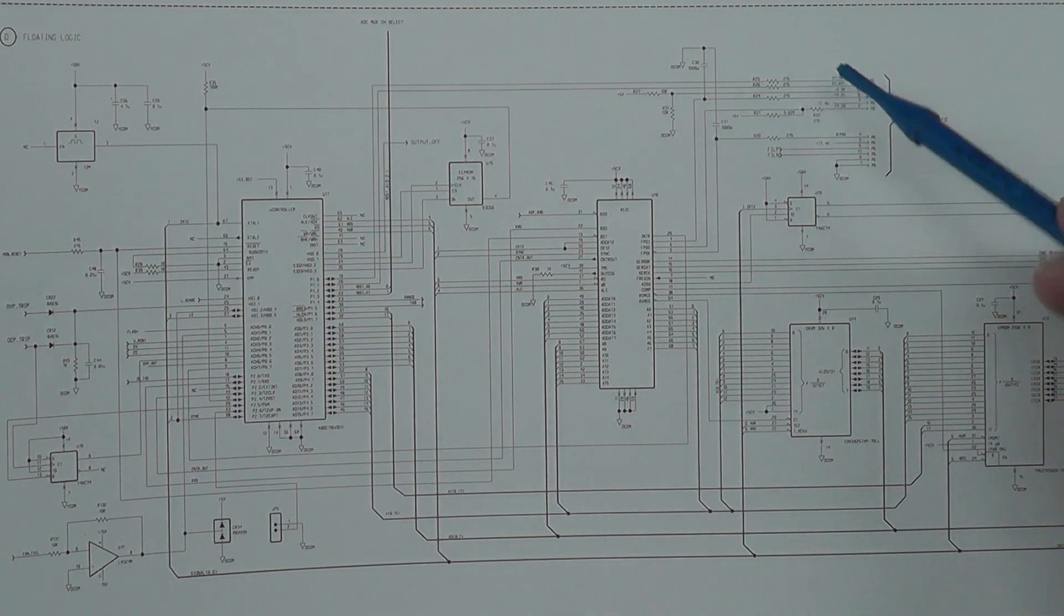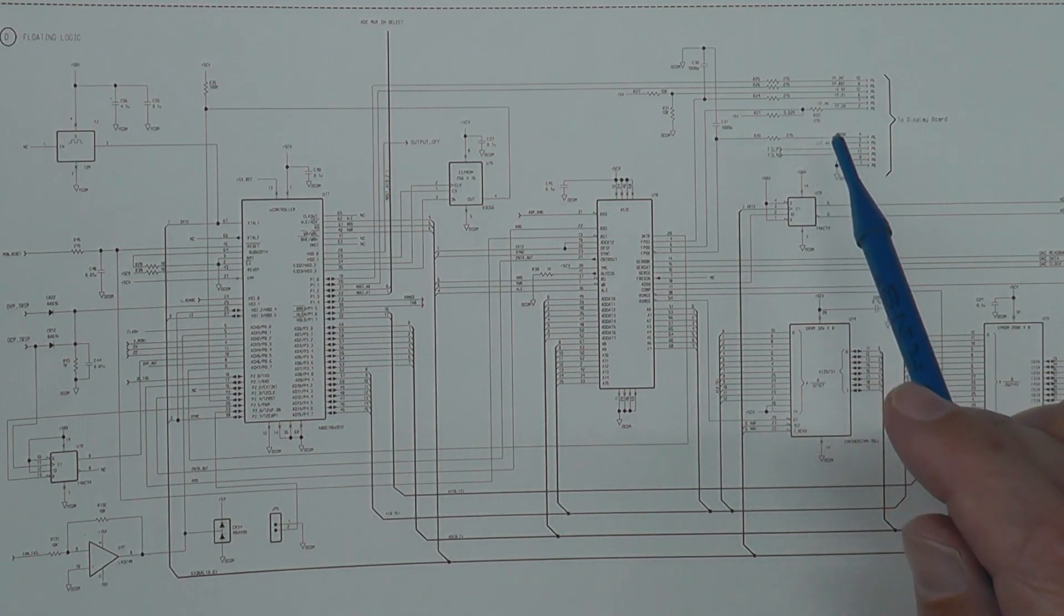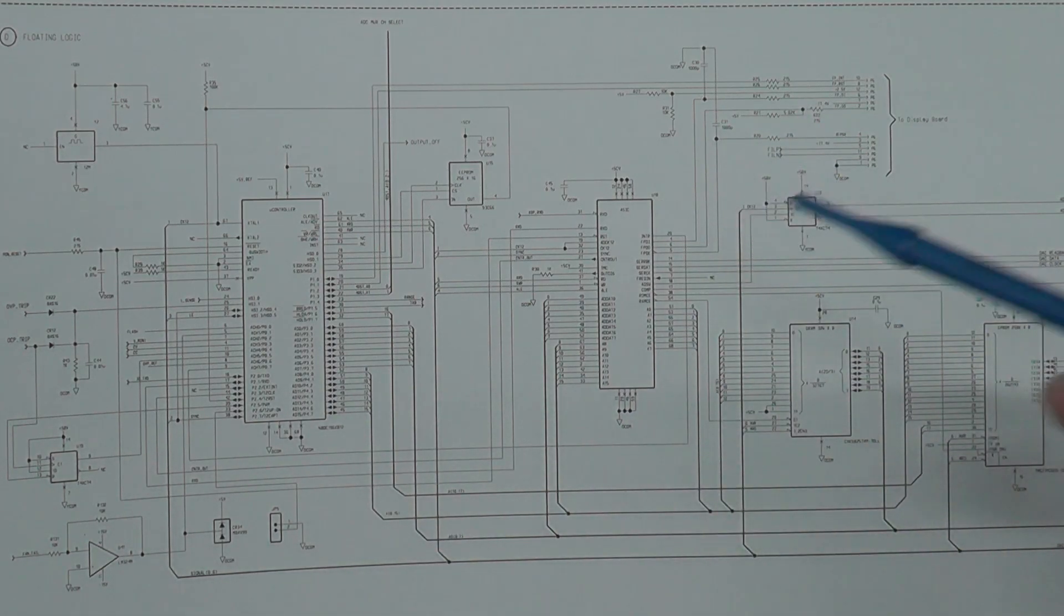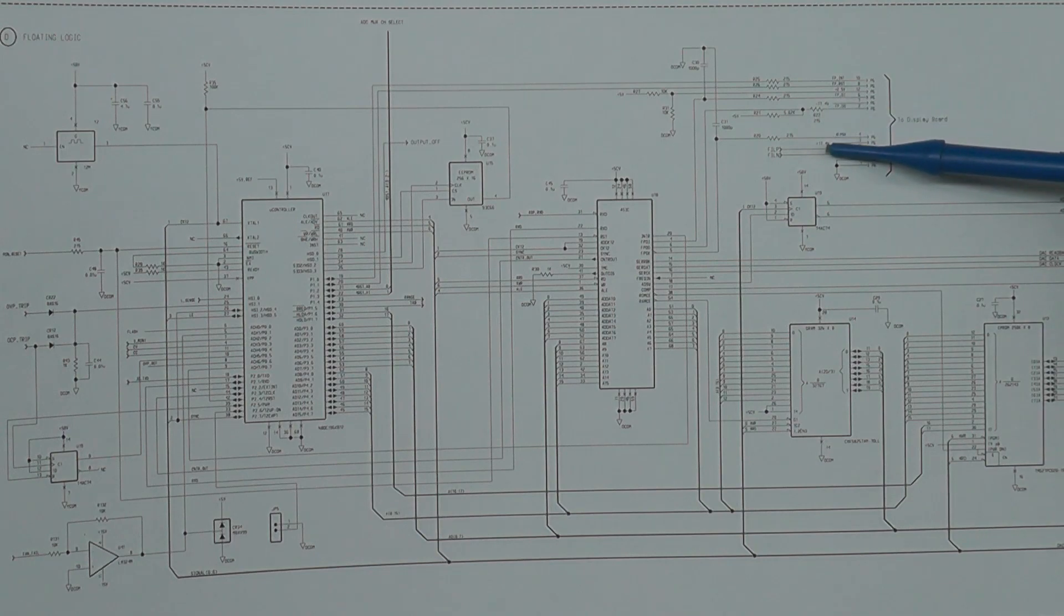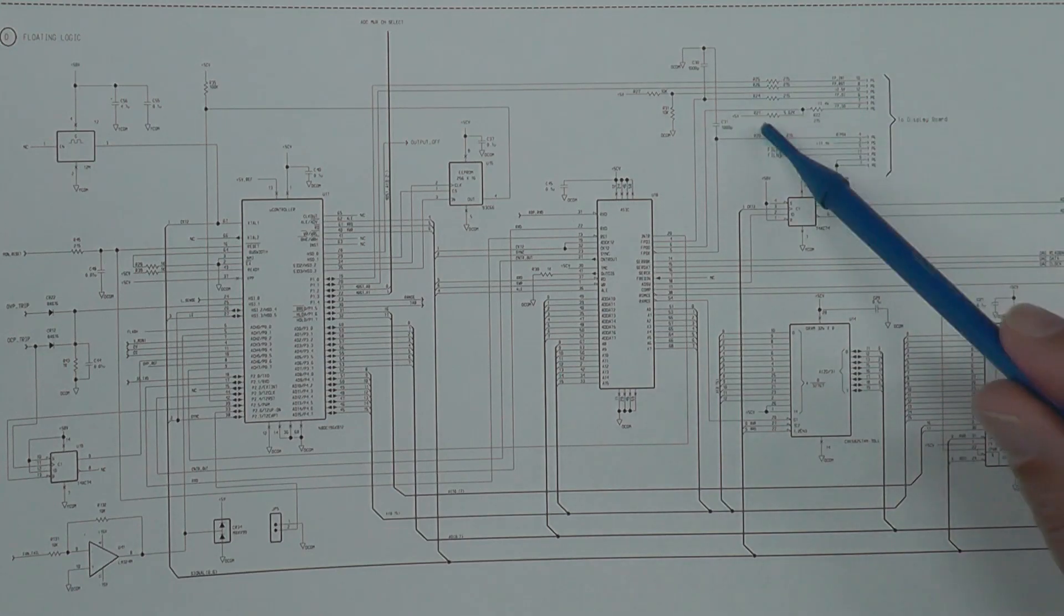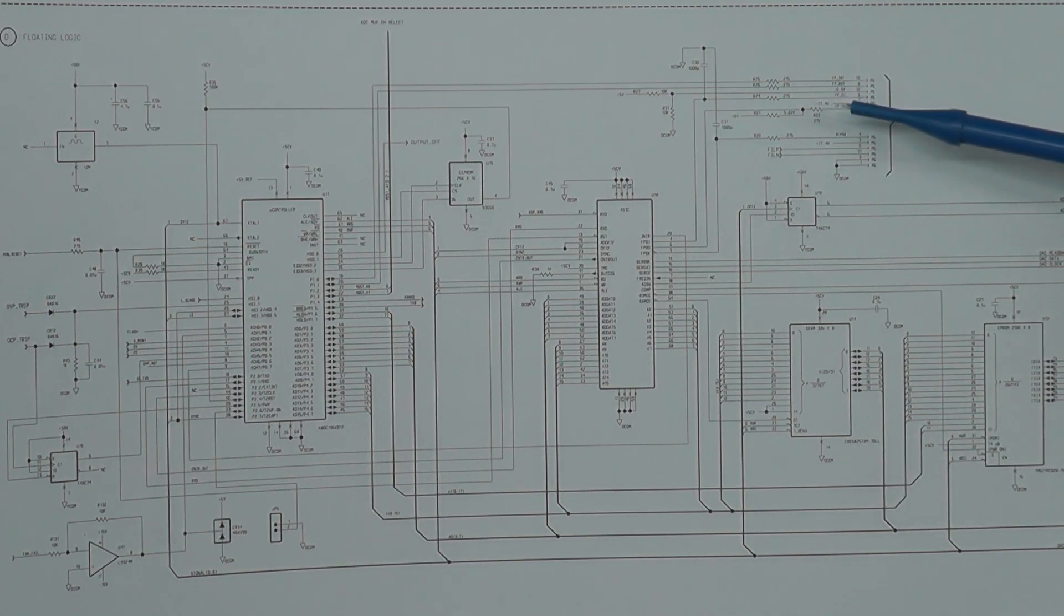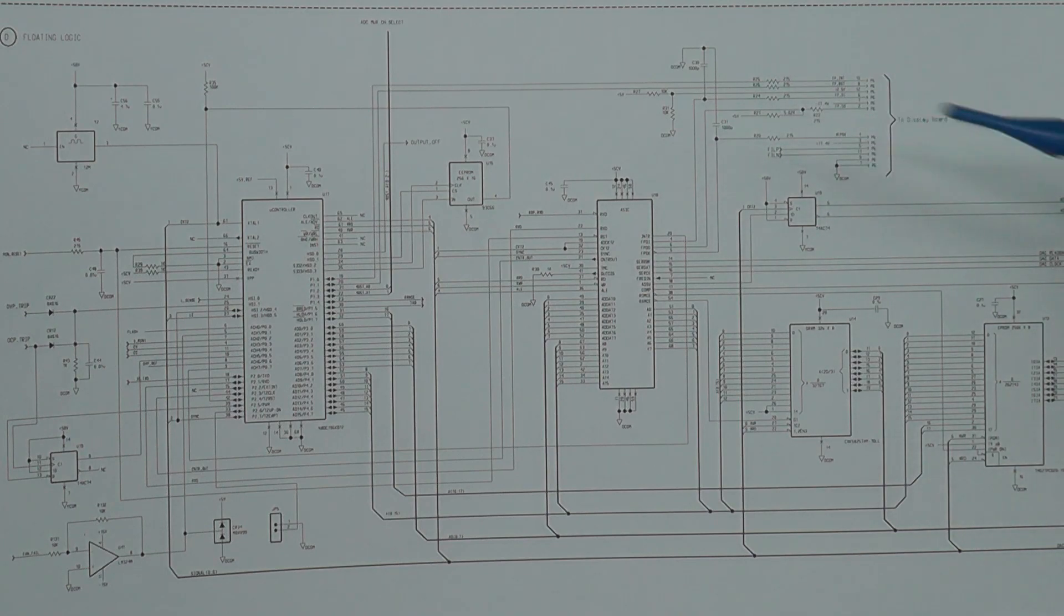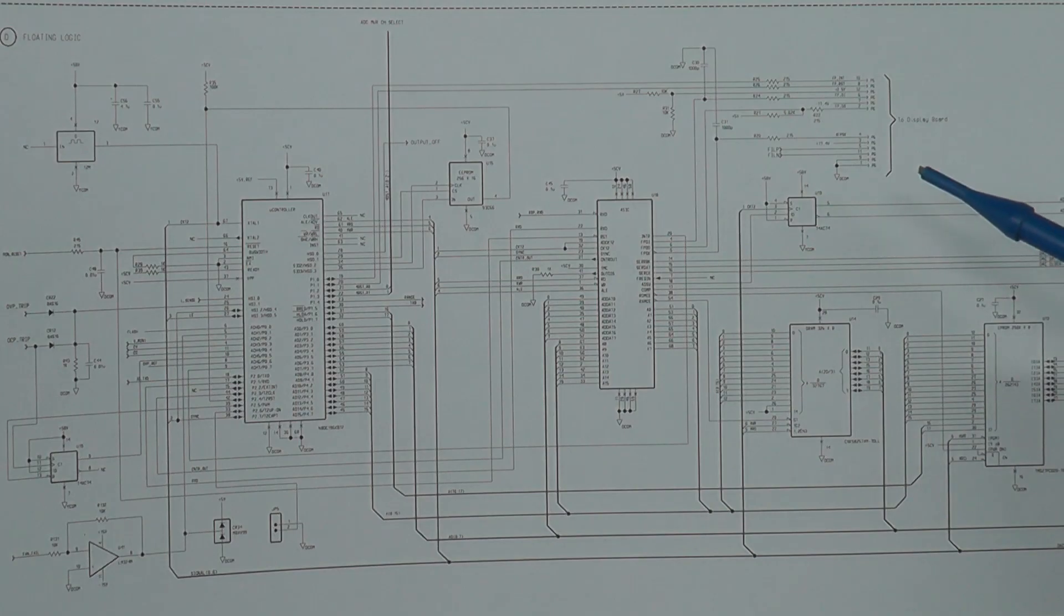So the first thing I'm going to do is scope the four wire interface to see if that's active. I'm thinking it won't be because the display is completely blank during normal operation. There's also this single beep every now and then - not sure what that is. You can also see the minus 17.4 and the plus 17.4 power supply going off to the display board as well. There's no real 5 volt supply going to the display board. The display board microcontroller, I think, references 0 volt to the minus 17.4 volt voltage level and is regulated down to minus 12.4 to give that positive supply rail. So let's scope the four wire bus and see if we're getting anything on that.